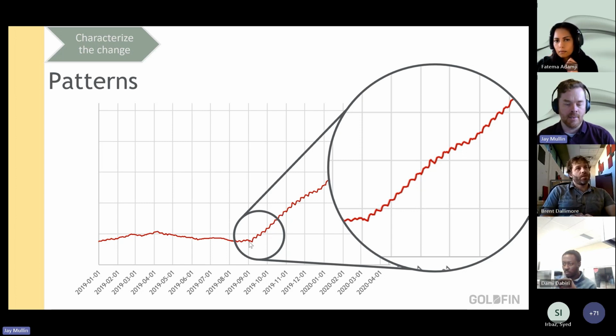So what that's telling us is the savings contributing to this upward slope are coming from those weekend days, where we're now using less energy on weekends than we did during the baseline period. So let's say they put in weekend setbacks on their BAS. So now every Saturday, Sunday we're saving energy, but nothing's happening during the week.